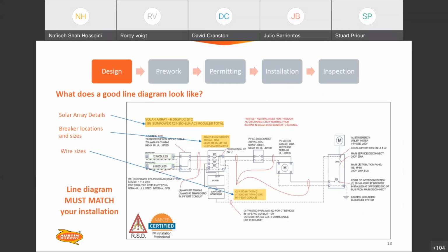So what does a good line diagram look like? This is a pretty good one here. You'll see you call out all the components within the system. You've got the module count. You've got wire sizing. You've got conduit. You've got your enclosures and their ratings. You've got details as far as overcurrent protection in all enclosures. And you've notated how you're interconnecting to the service. So in this case, you can see there's a 30 amp backfeed breaker at the bottom of the bus bar.